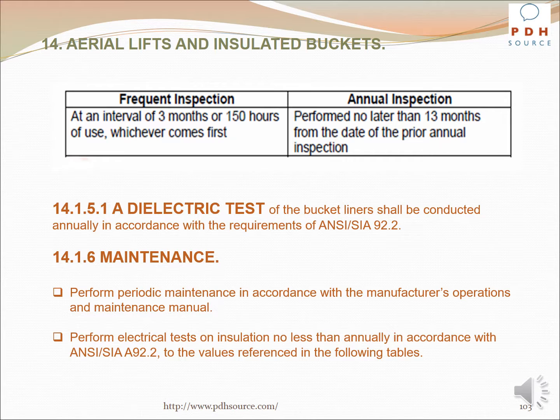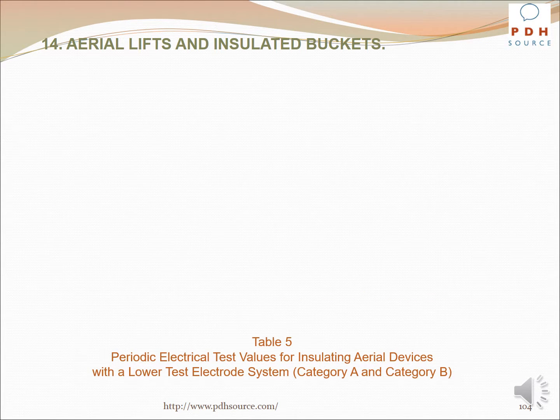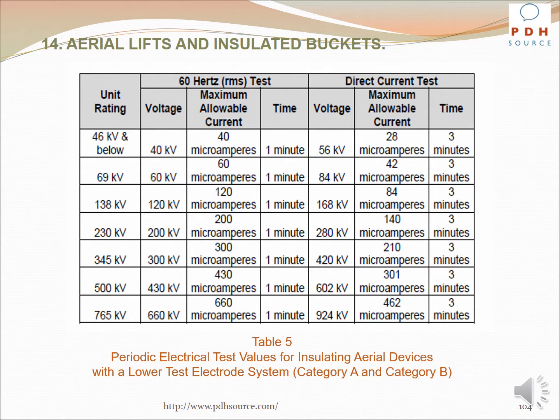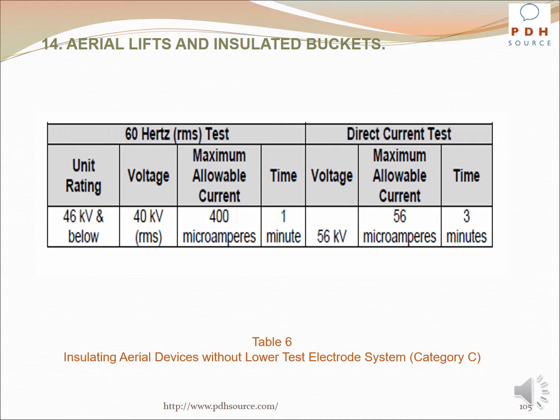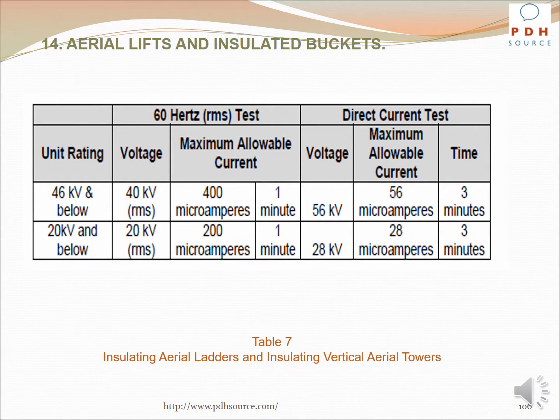Perform electrical tests on insulation no less than annually in accordance with ANSI SIA A92.2 to the values referenced in the following tables. Table 5 indicates periodic electrical test values for insulating aerial devices with a lower test electrode system, Category A and Category B. Table 6 indicates insulating aerial devices without lower test electrode system, Category C. Table 7 indicates insulating aerial ladders and insulating vertical aerial towers.